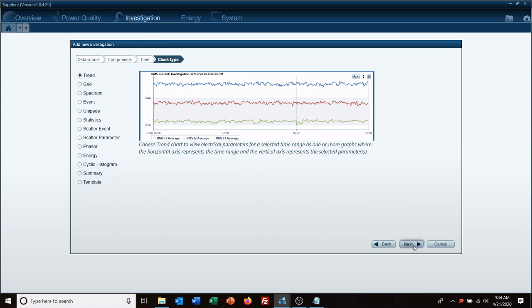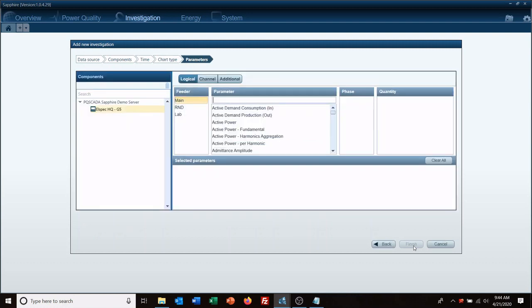So we're going to go with trend. So this is the parameter selection screen. If you have multiple feeders set up in your meter, in this case our G5 in the lab does, it's monitoring multiple buses. We're going to select main feeder.